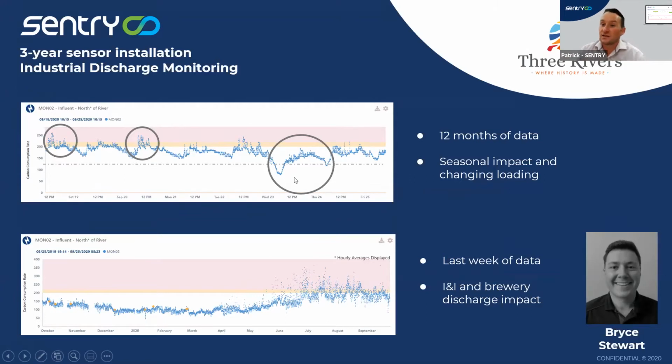But also when there are events like rain infiltration, you can see here on the low end, this was actually Hurricane Teddy as it passed through Prince Edward Island. And you can see how the additional dilution in terms of the incoming wastewater impacts and suppresses the activity at the front end of the plant for that 24-hour period.